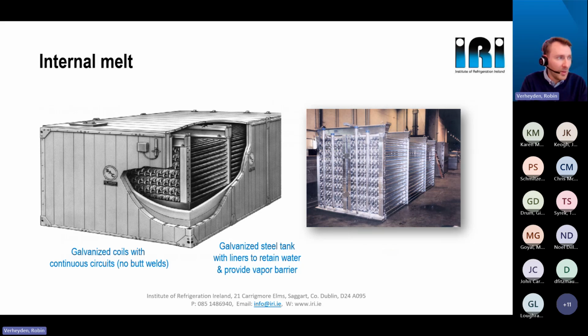A typical internal melt tank is a tank where you have outside panels and a liner on the inside, because it's a closed loop. We will use the coil to build as well as to melt the ice. It's a typical galvanized steel tank, and what we have here a lot is galvanized coils with continuous circuits, so no welds between the tubes, a complete circuit. Actually, it's the same coil design and the same procedure to assemble a coil as with our cooling towers.